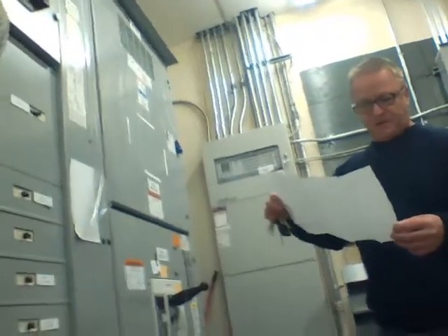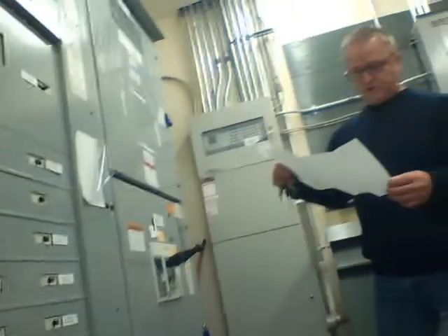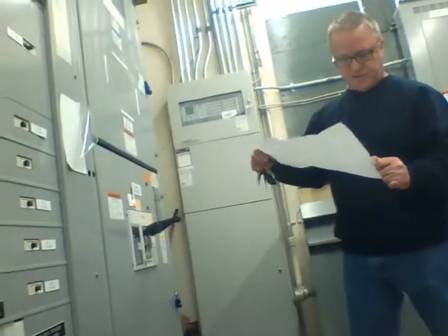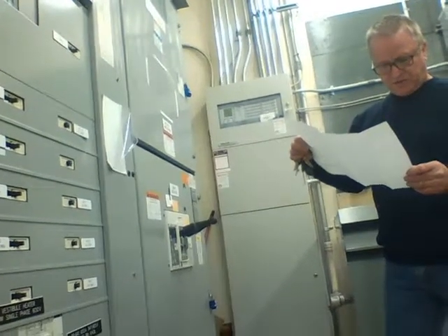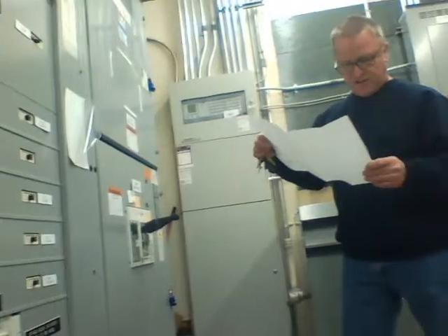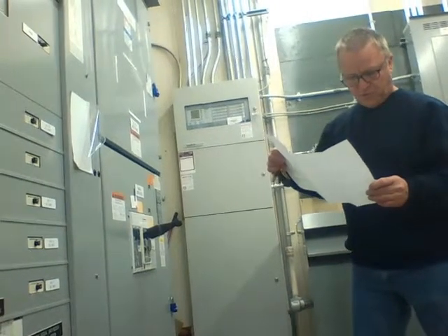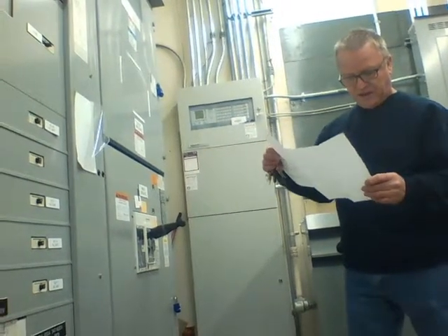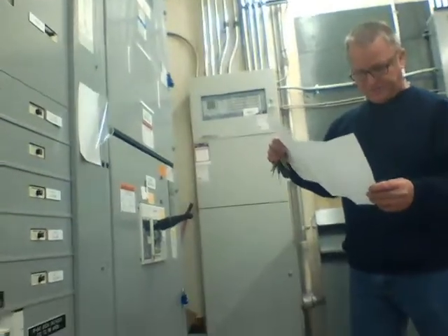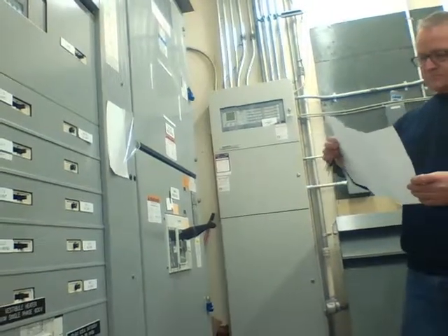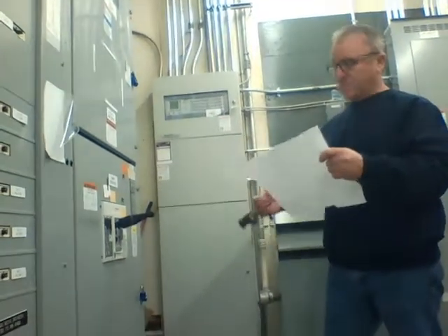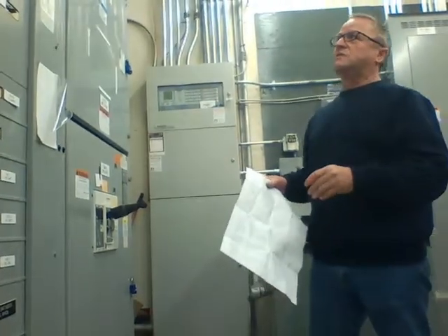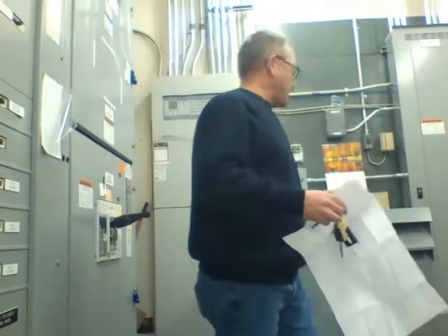The vertical portion showing all the breakers inside the dotted line. MS 6A1, 347/600 volt. It should say 1600 amp, not 600 amp. 3-phase, 4-wire, 35 kA interrupting circuit. So from this main distribution 600 volt, there are a couple of transformers in this room.